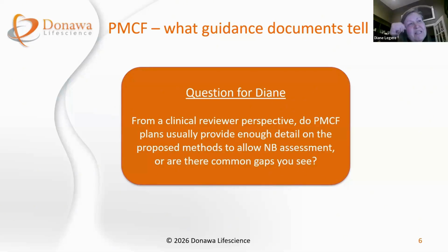Yeah, thank you for the question. I'm going to say the answer is really a mixed bag. I found higher risk devices tend to submit more detailed, specific PMCF activities. They follow MDCG 2020-7, as you mentioned. I will tell you, every single clinical assessor I know at notified bodies uses that guidance to assess PMCF plans. I don't know anyone who doesn't use it, maybe just by memory now.